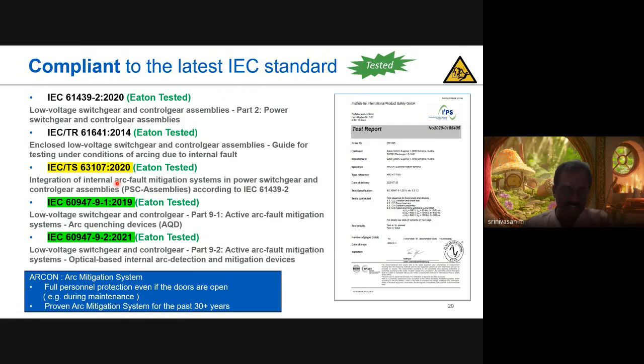We are proud to say that Eaton is one of the leading manufacturers globally. We got the type test certificate for IEC 63107 for our Eaton switchboard system. You can verify with other manufacturers also; so far, up to our market intelligence, they don't have this. And this is very important to increase the safety level of the switchboard, especially in the event of an internal arc condition.